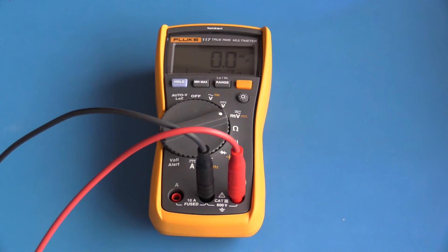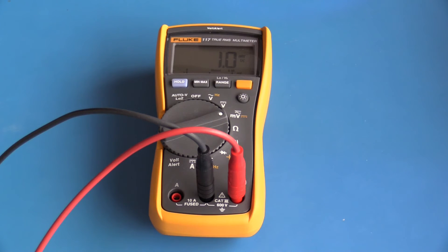The Fluke 117 also has a millivolt range for both AC and DC. Millivolts AC is default, but I can select millivolts DC by pressing the option button. Using my reference, this is one millivolt DC - the resolution is 100 microvolts. And I can step up in 100 microvolts steps. This is one and a half millivolts, this is two and a half millivolts, five millivolts, 10 millivolts, 50, 100 millivolts.